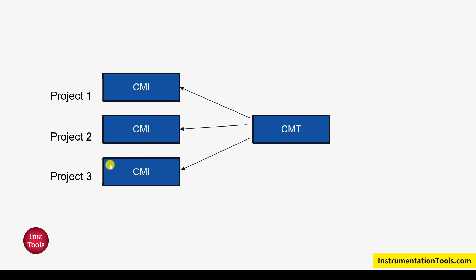This template logic will be implemented in every user project as required. For standard logics — for example, analog monitoring, valve, or PID tuning blocks — the logics can be written in a single CMT. That CMD will be instantiated in projects by changing the name, which is termed as CMI — control module instance.